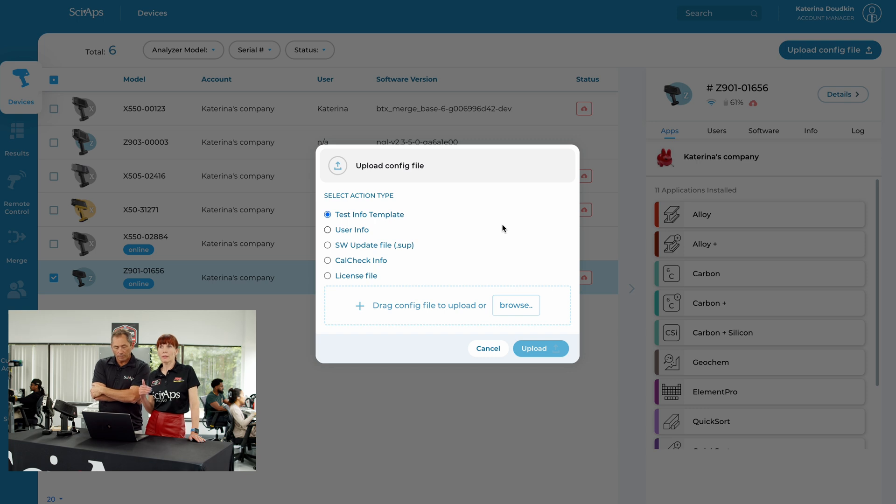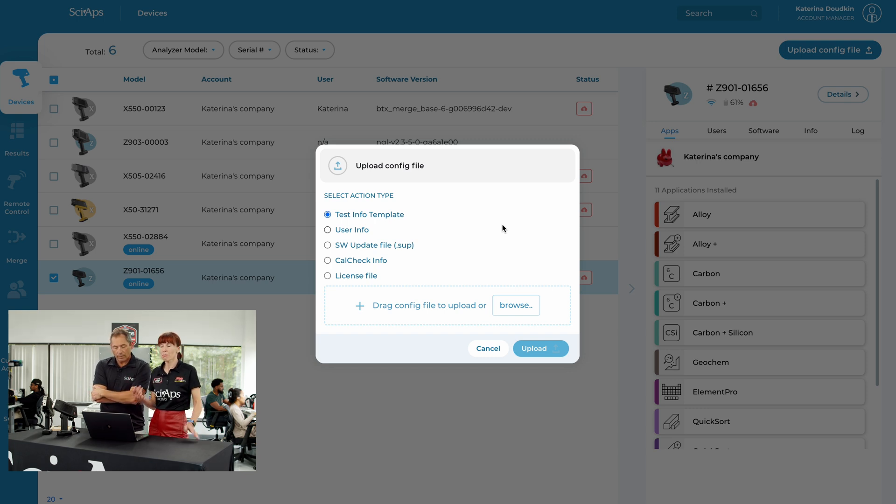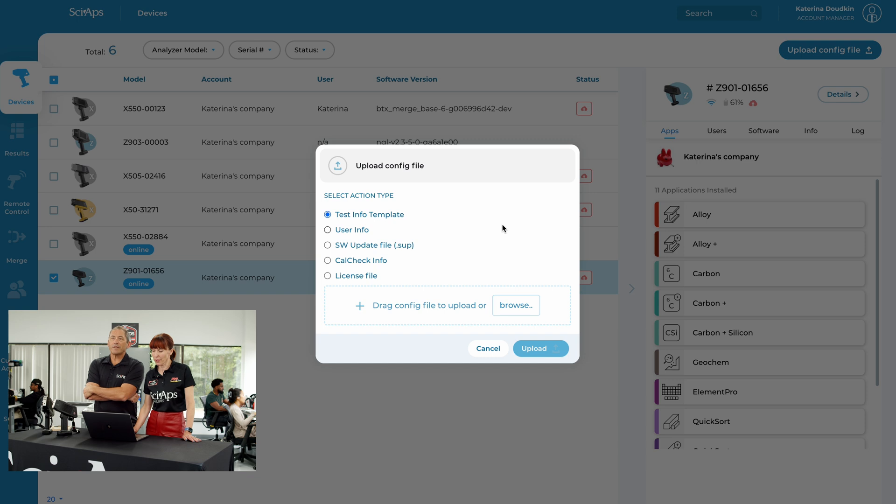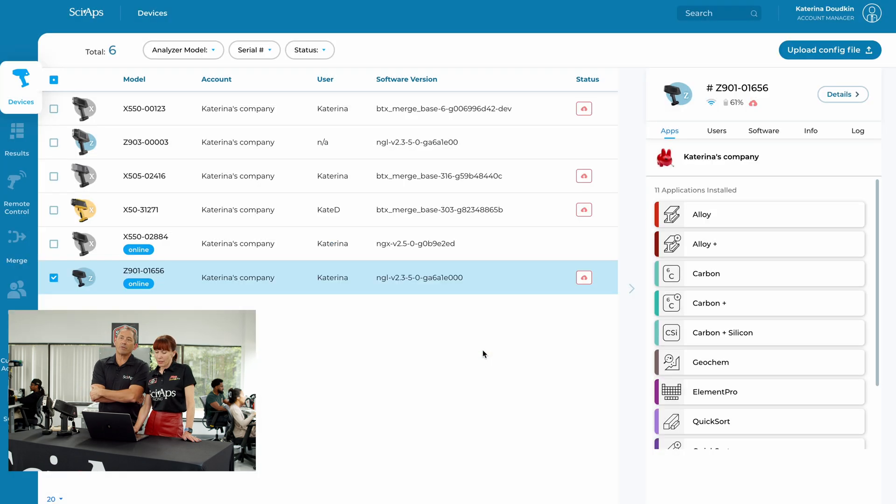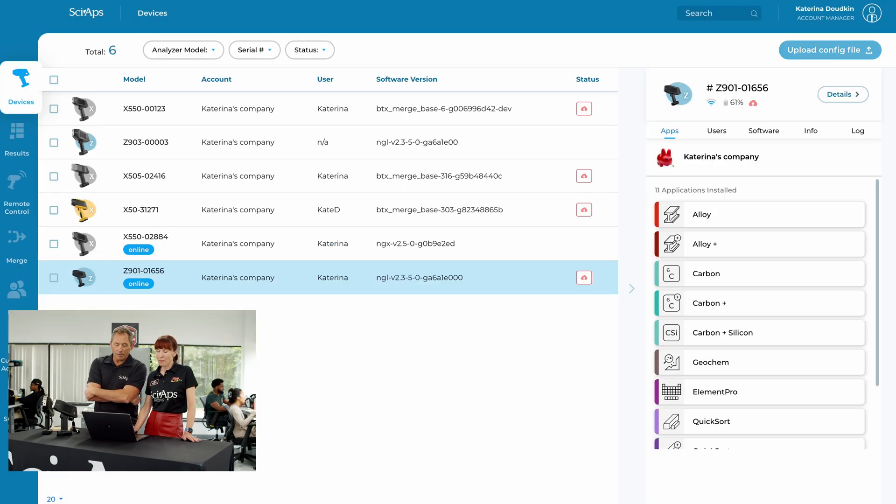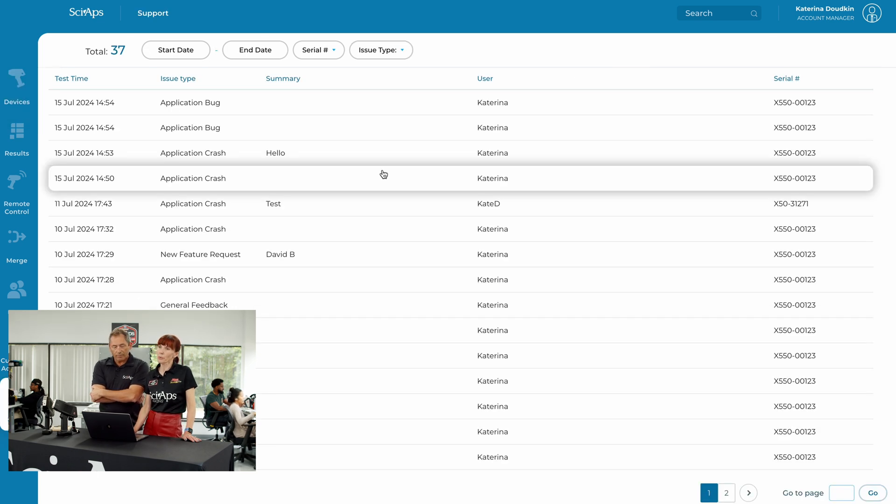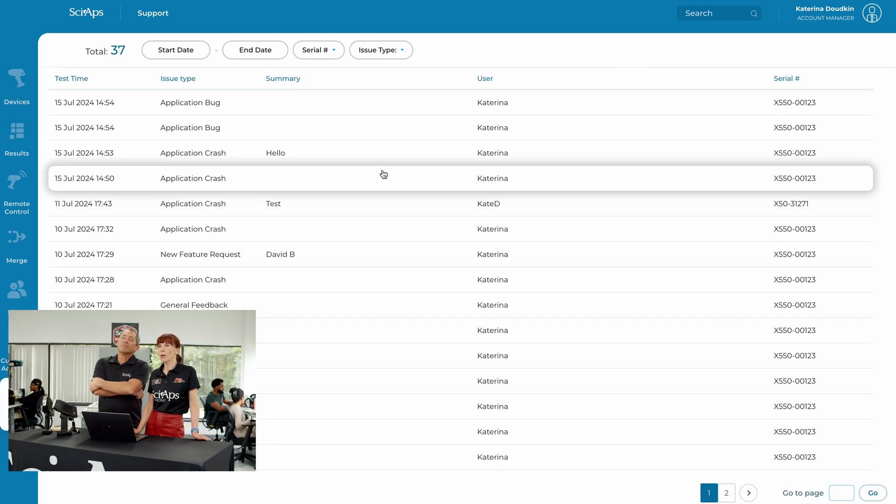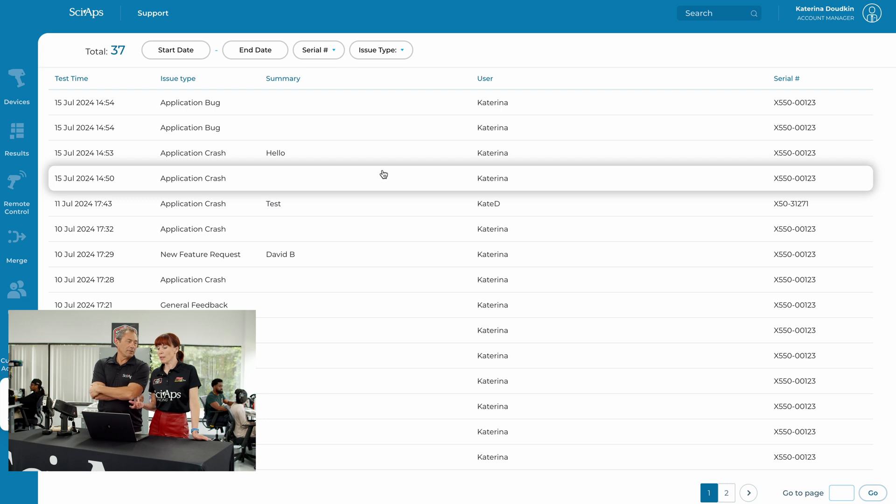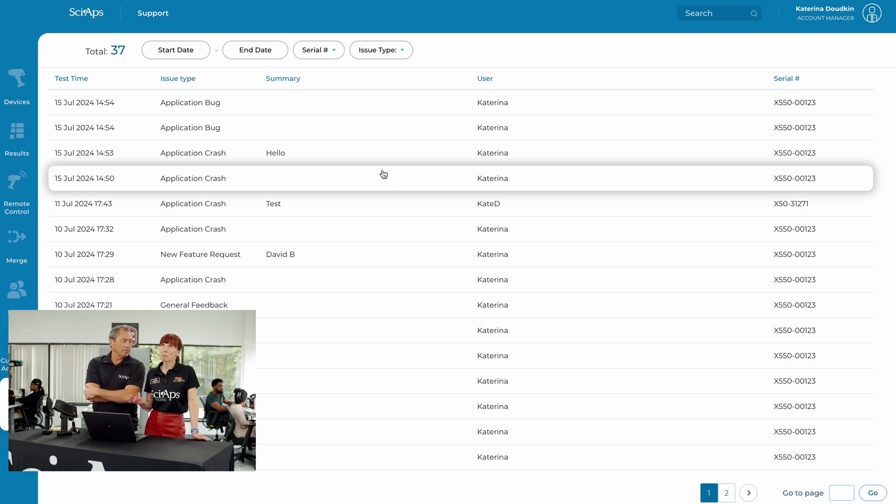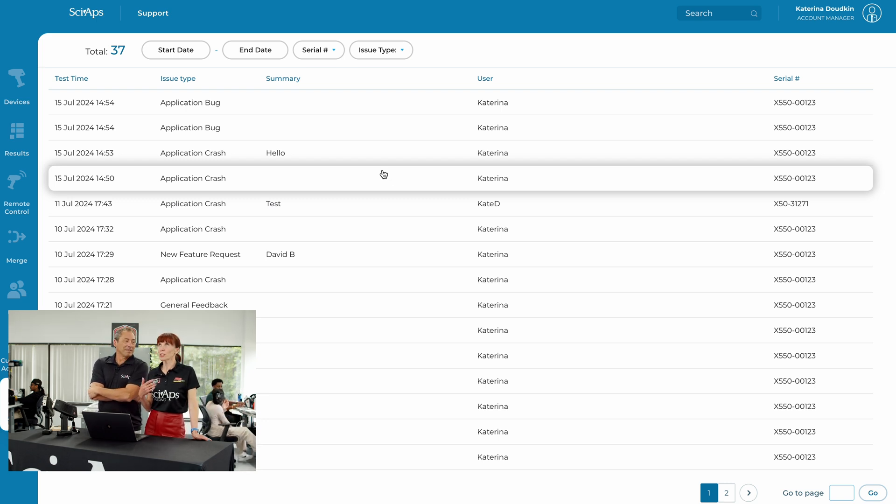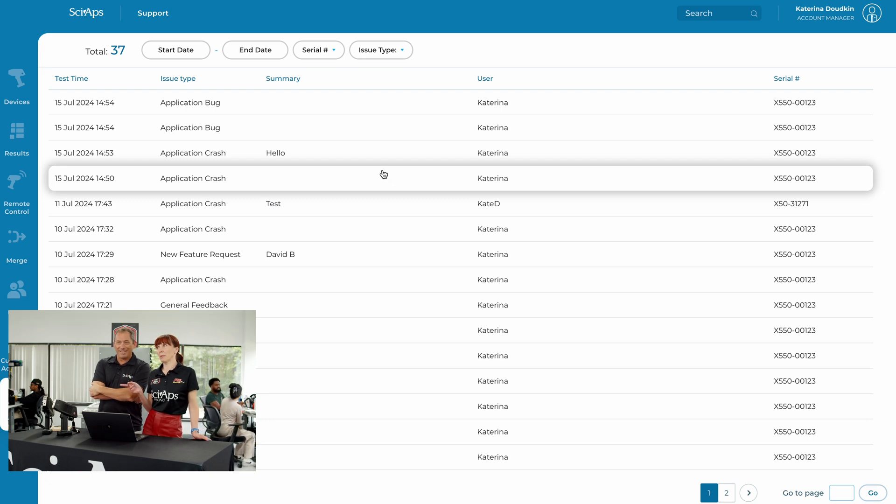And from there, you could accept the software updates, same way as you do on your phone. So you don't have to send your instrument back anymore. You don't have to wait for a technician to come out and upload. Very nice. Also what we have, we have bug reports. On analyzer, we added a new feature that allows you. You always told me your software didn't have bugs. Well, that's not our bugs. Back to manager. Yeah, let's blame electrical and mechanical. I like doing that.